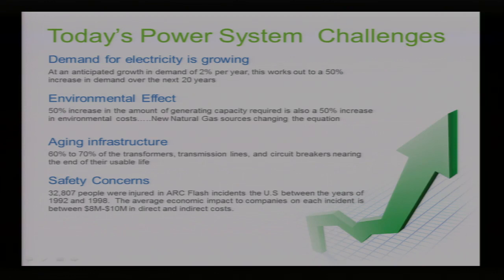There are new technologies now that can detect an arc flash. Think about the characteristics of an arc: number one, it has bright light, so light becomes one of the primary detectors of an arc flash, like when a circuit breaker is told to open and doesn't quite get there and blows out the front door. Detecting light is very fast, but turning on a light in the room is also light, so how do you differentiate? Well, an arc also has sound, so correlating sound and light is another mechanism for detecting arc flash in electrical switchgear.